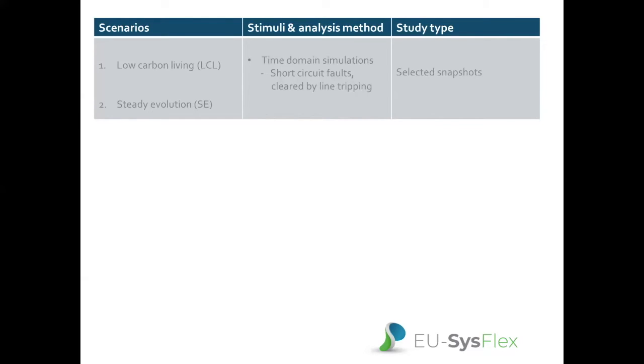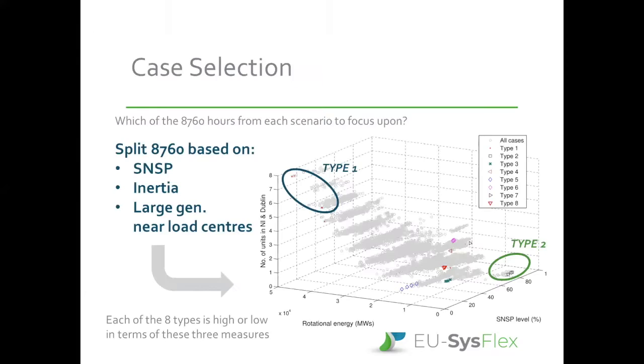For today, I'm going to focus on the LCL results as that had the highest renewable penetration and probably is of the most interest to everyone. So slide, please. So here you have a 3D plot of all the hours of operation that came out of that Plexos production cost model. They're scattered with three metrics: SNSP, which, as Hassan mentioned earlier, is the penetration level of converter interface generation into the system. You then have rotational energy or inertia on one axis and the number of large units near the load centres in Northern Ireland and Dublin. We felt these were three good measures for breaking out each snapshot and then splitting them into types. We defined high and low in terms of each of the three measures, and then each type was effectively high or low in one of those measures.